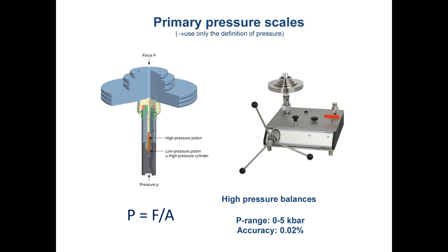Now we come to more hands-on subjects. Primary pressure scales: what is a primary pressure scale? It is a scale based on a thermodynamic definition of pressure — it doesn't involve anything else, just thermodynamics. At some point it always comes back to force divided by surface. There is a machine that allows you to calibrate pressure devices and give you a truly absolute value of pressure consistent with the thermodynamic definition.